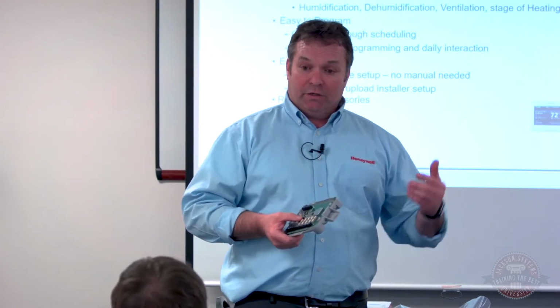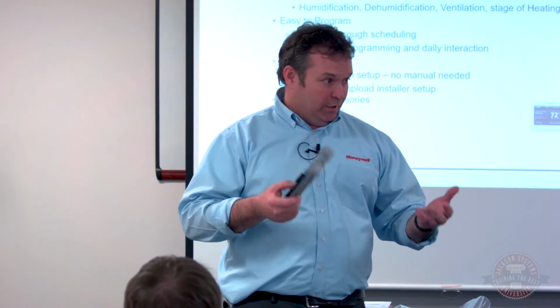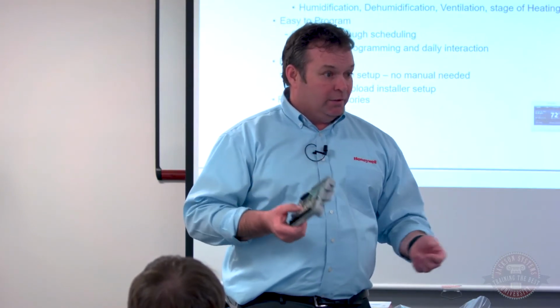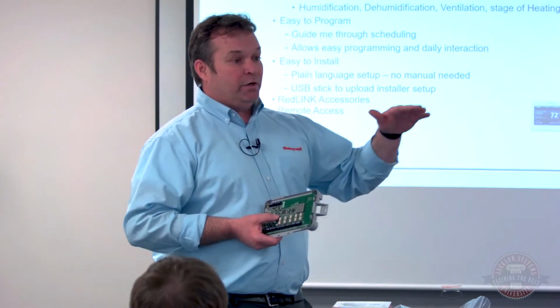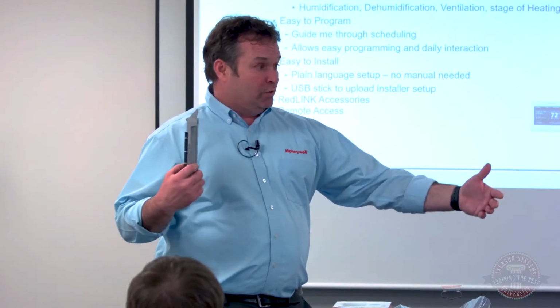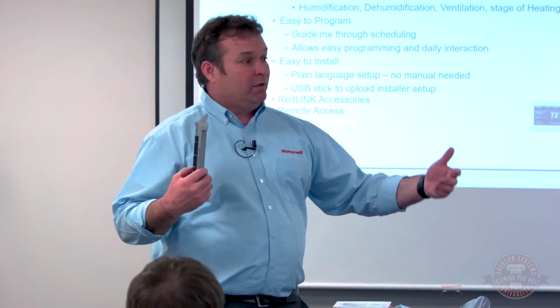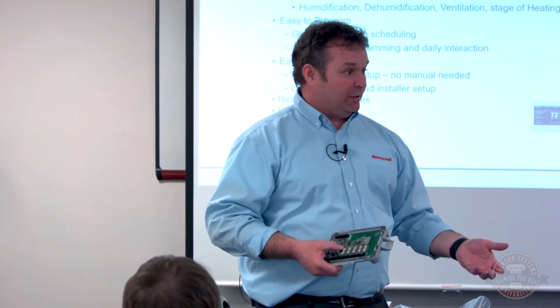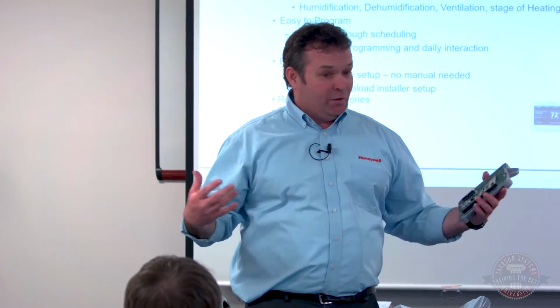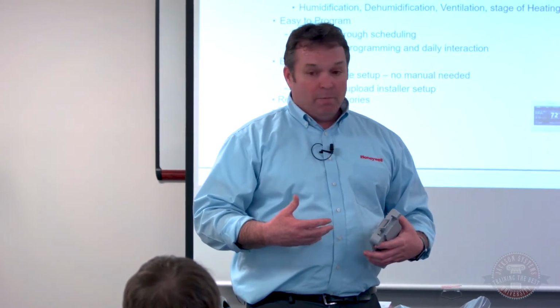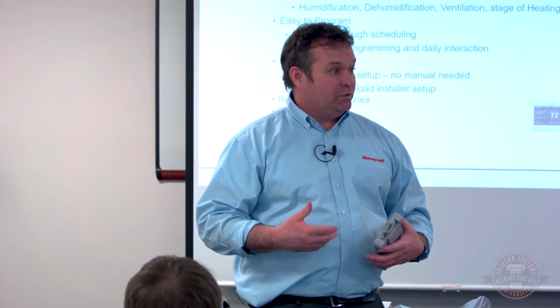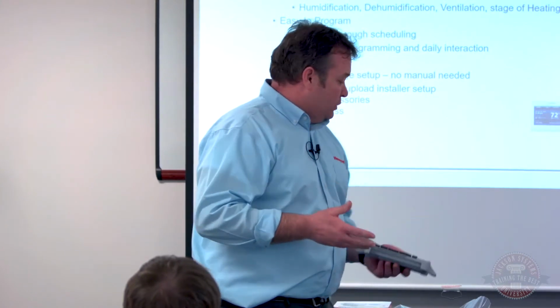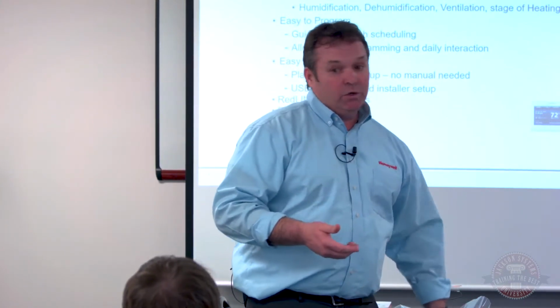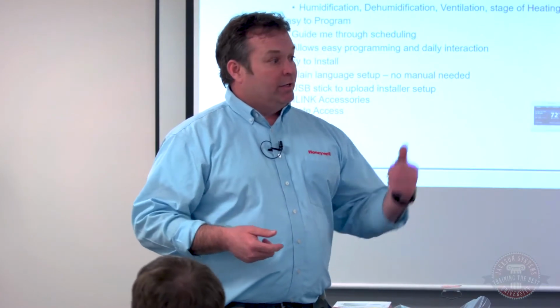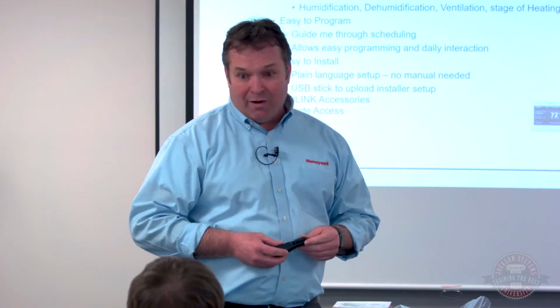Most systems run 18 to 20 degrees normal delta T on cooling. So you can do your heating delta T and your cooling delta T, and if it gets out of those normal parameters, it'll email your company, email your homeowner that you need to roll a truck out there. So it just really keeps you tied in with that homeowner, and keeps them from running to somebody else, because you're going to take care of their system. And so if you had a doctor that could tell you, before you have a heart attack and die, it's going to send me an email and I'm going to have an ambulance come to you, you can do that with this system now, right?